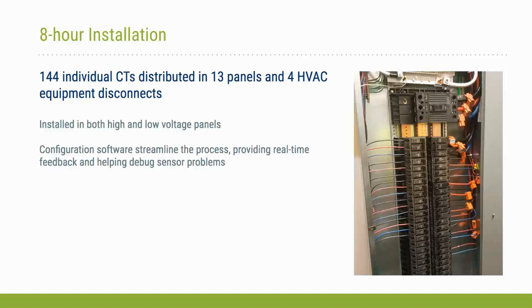So as you can see, it's definitely a lot easier than the standard metering technology. And we were able to install this in both high and low voltage panels. The vendor provides software that streamlines the process really well. You're able to see in real time as you are connecting the meters, the sensors, in this case the wireless CTs. You can see real data and debug whether the CT is working or not. So that helped us debug any problems we had, and it made installation a lot easier. So next slide, please.